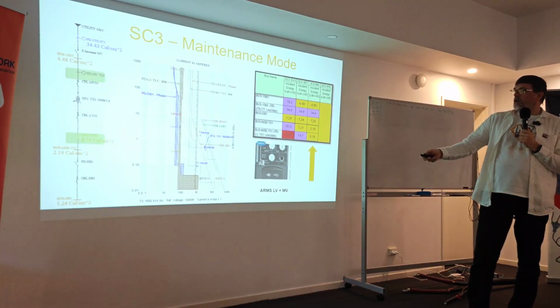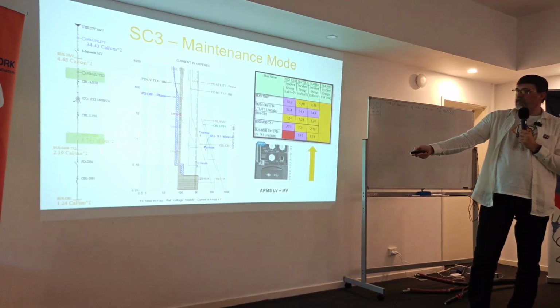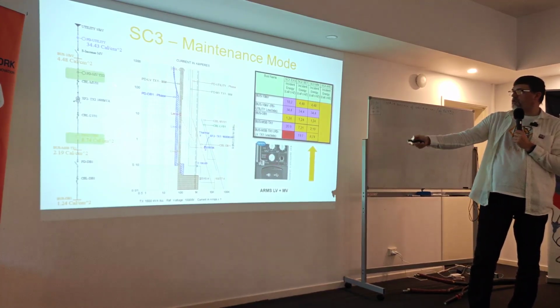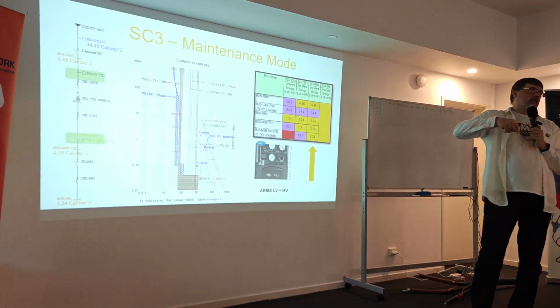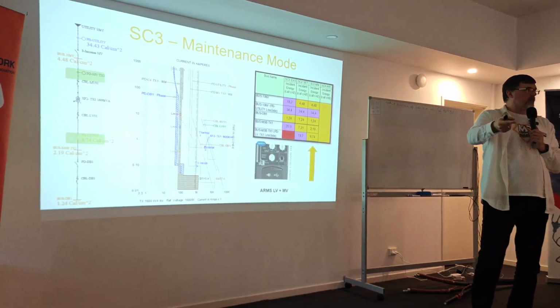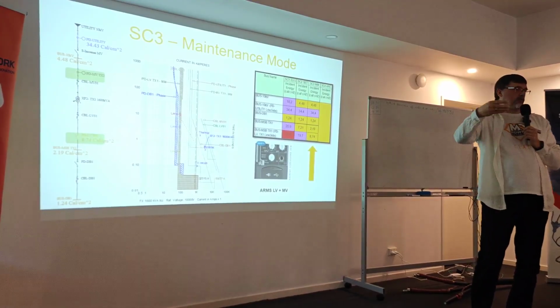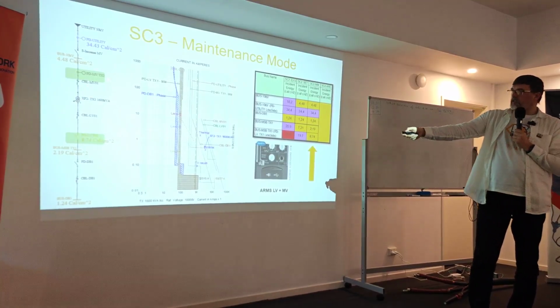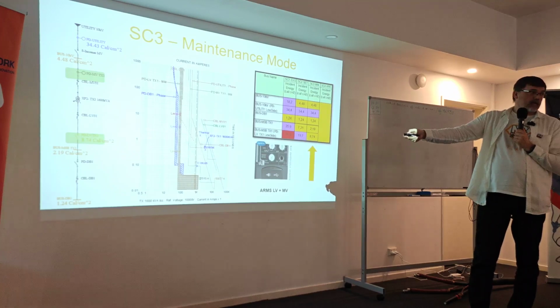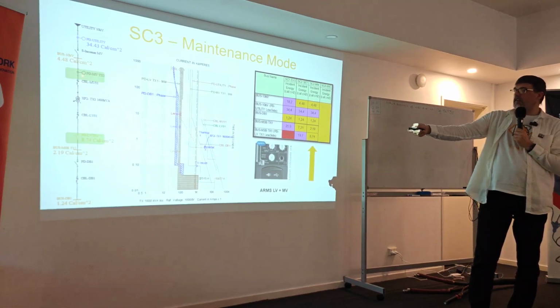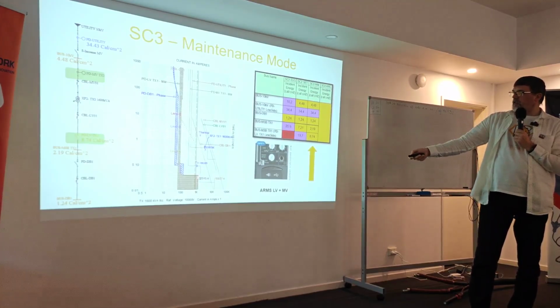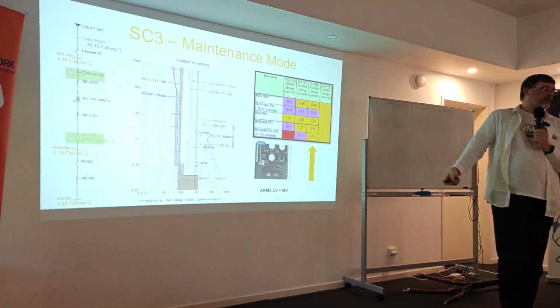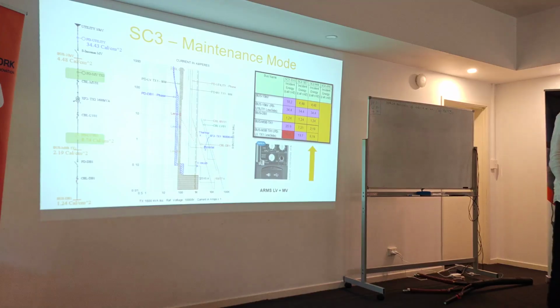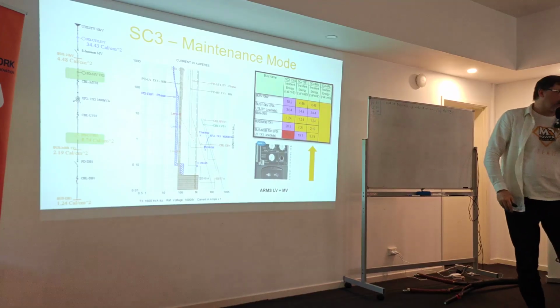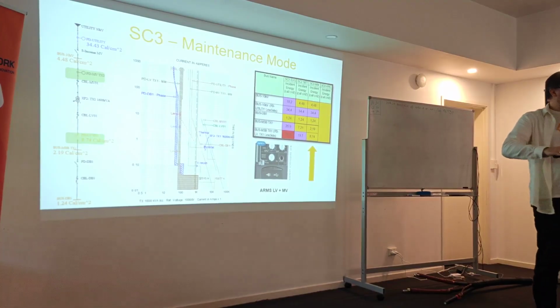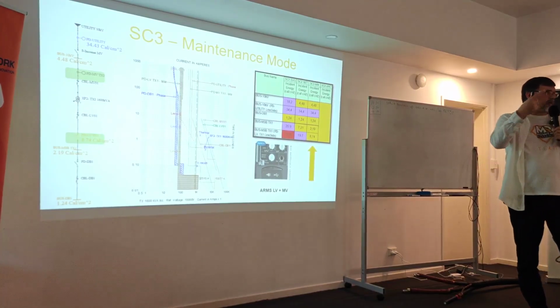And I did 2 things. I did the same because this is the default in the trip unit here, but I also made it for the medium voltage relay, which is this part of adaptive settings. So you can program the same function in the relay, you just need to know what to do, but you can program it, which is a custom-made thing, if the relay is smart, yeah? So I have to propose changing the relay here. And then drop the settings, but I didn't drop them to the very minimum. I dropped them to the point where we can still energize the transformer. Probably 1 out of 2 times we will energize it, because it's really on the bottom, if we have to, yeah? Because the transformer is running.